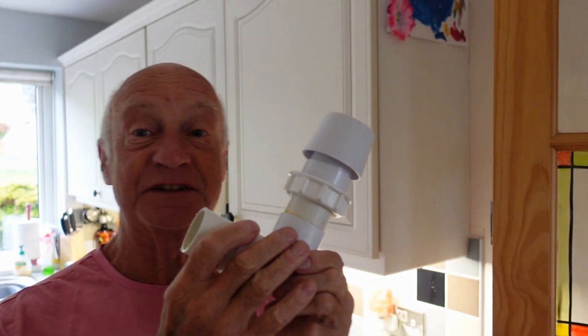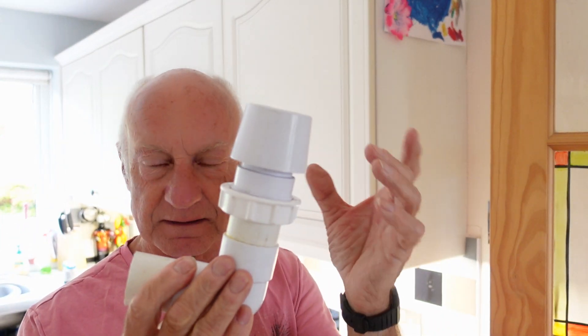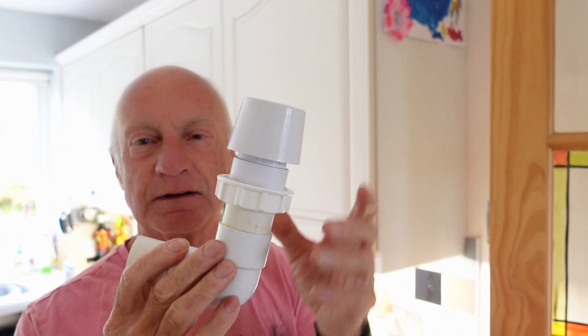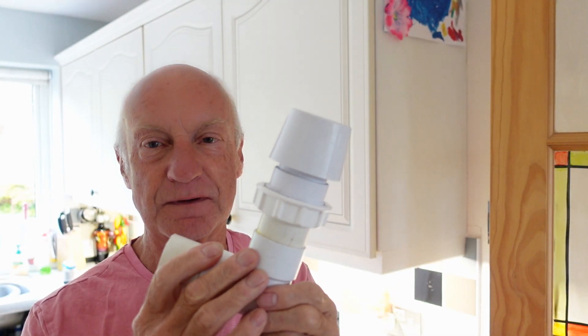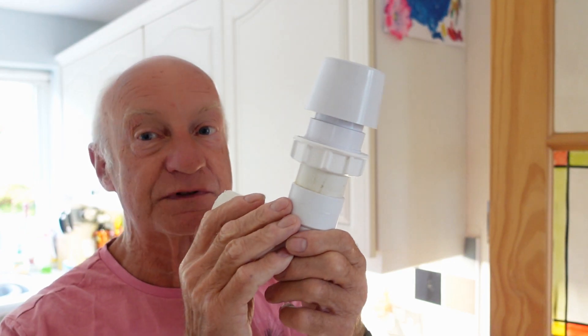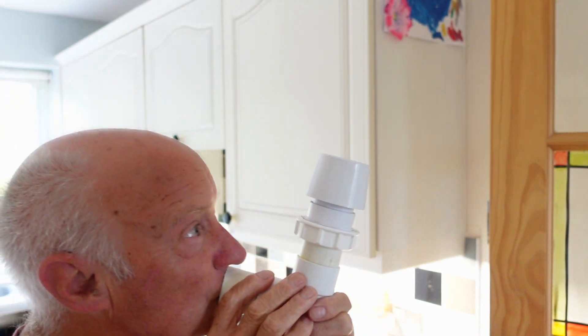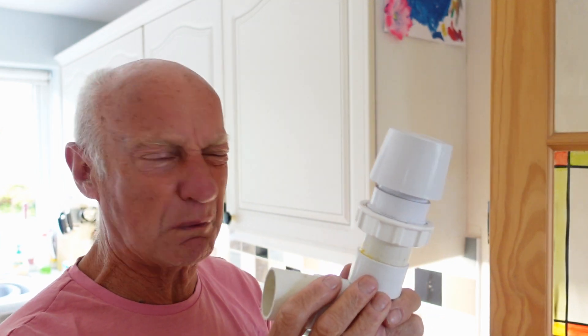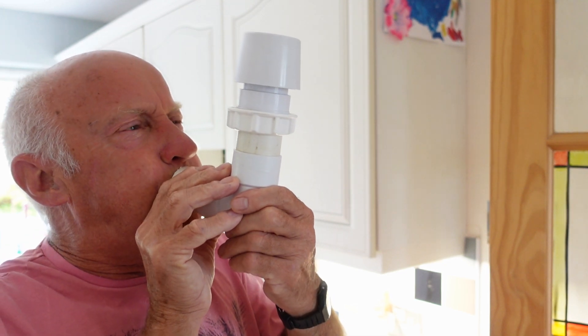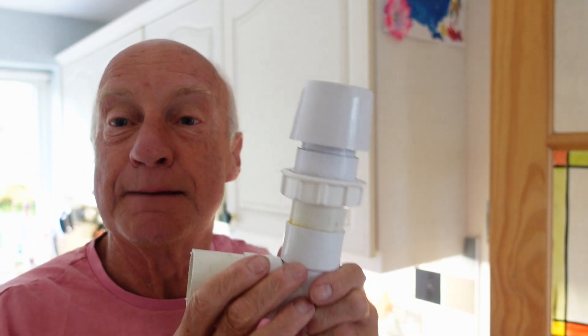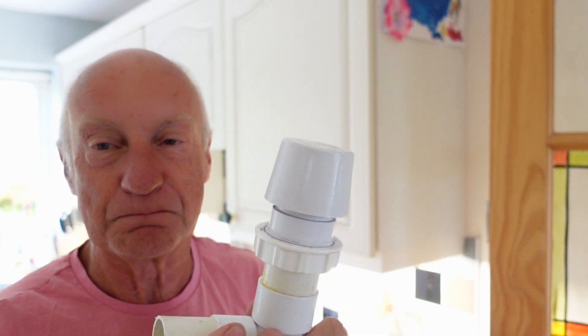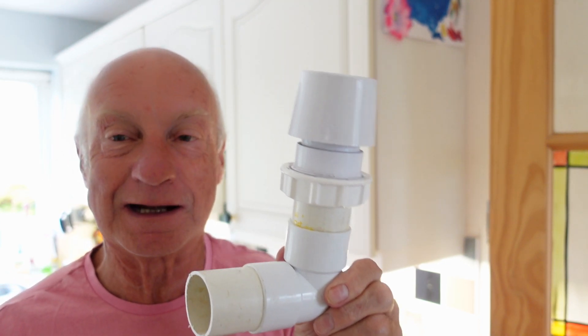I'll show you how these things work when they're fitted. They don't allow water out but they allow air in. First I'm going to suck air in - yep, certainly works, always smell horrible. But I'm going to try blowing it now. Impossible, can't blow up there at all. So we know the thing works really well and it's going to let that air in.